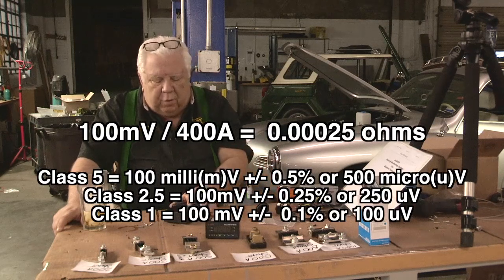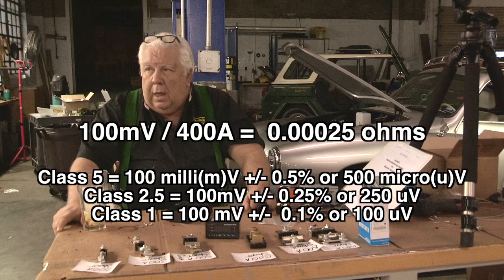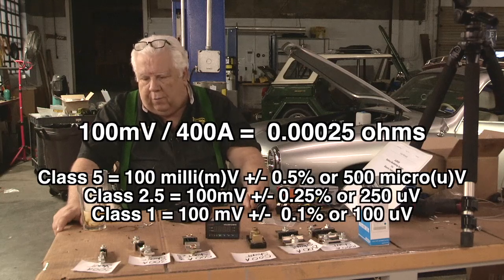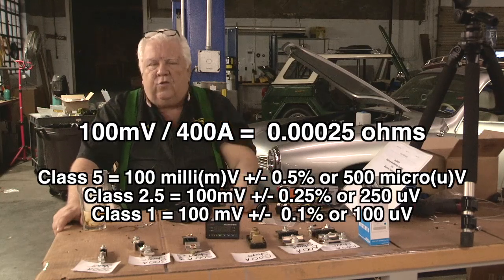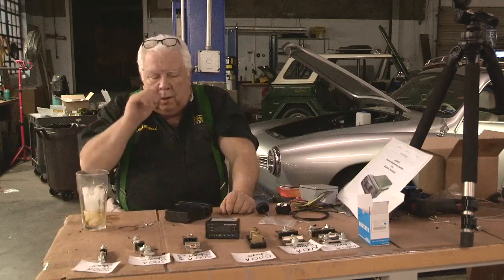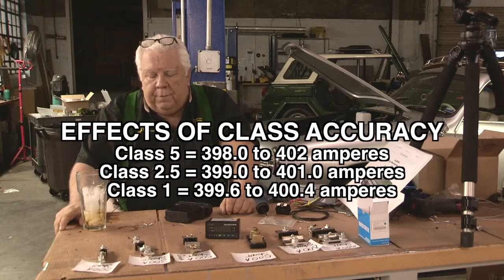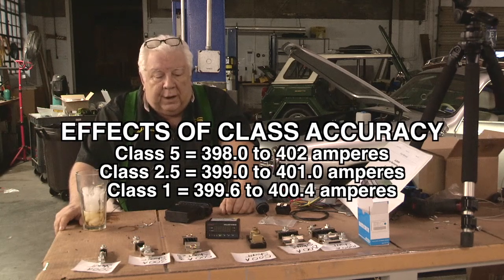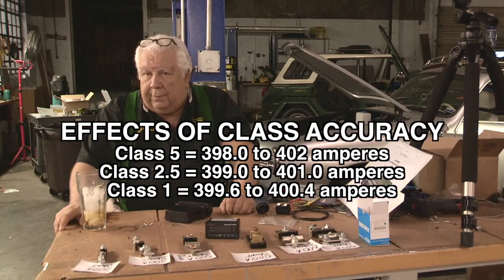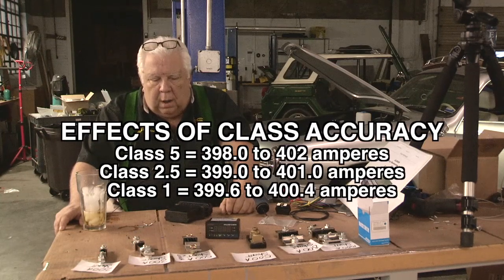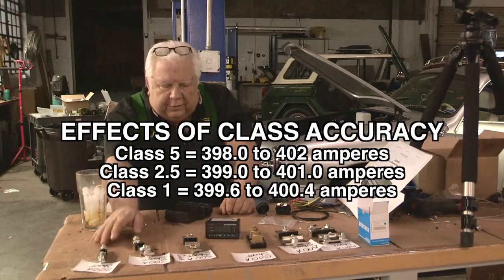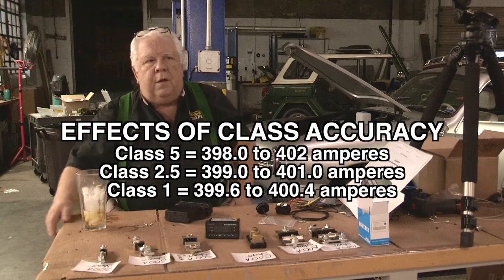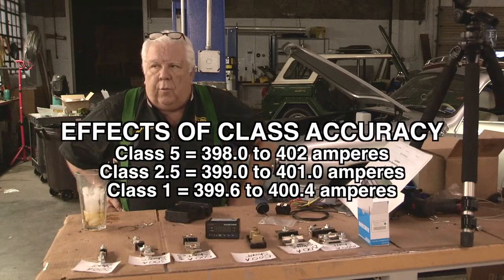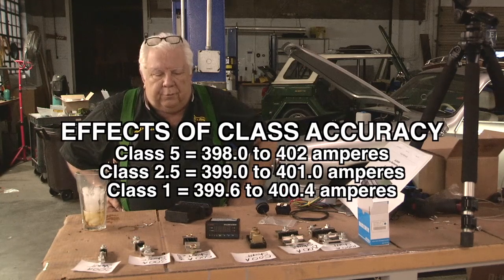For our JLD505 project, I've just ordered 100 IMCO 400 amp 100 millivolt shunts, but they're Class 1, and that is 0.1% plus or minus on the resistance of the shunt, and so it's accuracy. And so by going to 100 millivolts on 400 amps, I get better resolution, about 4 amps per millivolt, which is down like this 200 amp, but with the ability at 400 amps to easily go 600, and that covers almost everything we would do with a high-performance electric vehicle system.